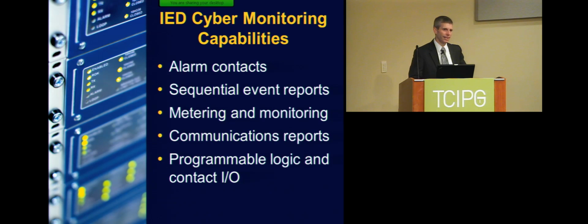Communication reports, all IEDs, or at least the ones we're using for line current differential or signaling or that, have communication reports, and they'll tell us the availability of the channel. The availability of a protection channel should be at five nines. If we're seeing that there's intermittent problems with the channel, like our availability is going down for whatever reason, whether it's the equipment is starting to fail, which would require us to go out and fix it, or I'm being spoofed, or some other means where the channel is being interrupted, we can use these communication reports to flag alarms and use that as indication that there's a problem going on.